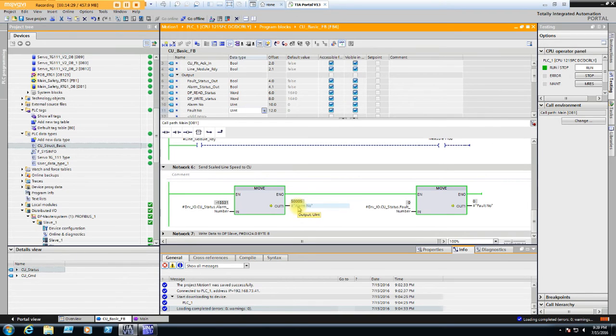Well, what happens when you look at an integer above 32,000? Well, if it's a normal integer, what you see is a negative number, because the 15th bit, or the last bit, however you want to count, 15 or 16, but the last bit is the sign. So if it's a 1, it's a negative number. If it's a 0, it's a positive number.